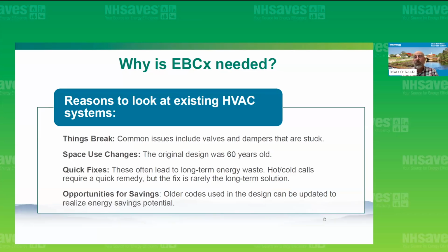Also, you find space use changes over time in buildings, and those usually focus on more cosmetic changes, likely not bringing the HVAC along in a balanced way. And when staffing is stressed, quick fixes are needed to put out fires when they're getting inundated with complaint calls. These are commonly forgotten or rarely looked back at, to see how that quick fix might have impacted the system when it moves from a heating to cooling mode, or vice versa. And commissioning can also identify areas where the original design just didn't incorporate common opportunities that we would use today. If those can be retrofit with minimal intrusion, that's another great opportunity for energy savings.